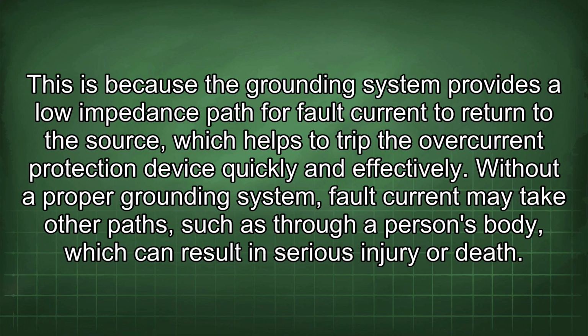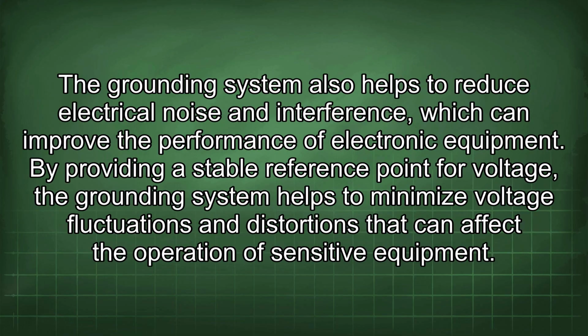This is because the grounding system provides a low impedance path for fault current to return to the source, which helps to trip the overcurrent protection device quickly and effectively. Without a proper grounding system, fault current may take other paths, such as through a person's body, which can result in serious injury or death. The grounding system also helps to reduce electrical noise and interference, which can improve the performance of electronic equipment. By providing a stable reference point for voltage, the grounding system helps to minimize voltage fluctuations and distortions that can affect the operation of sensitive equipment.